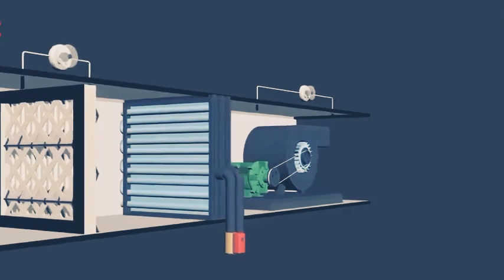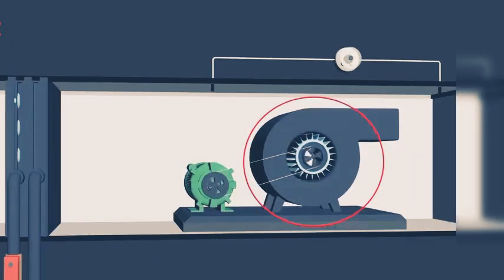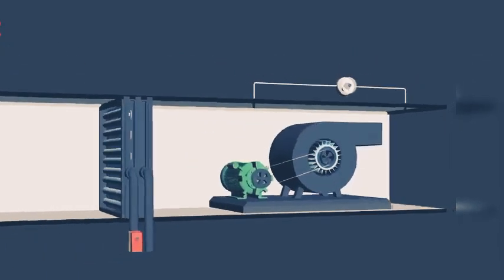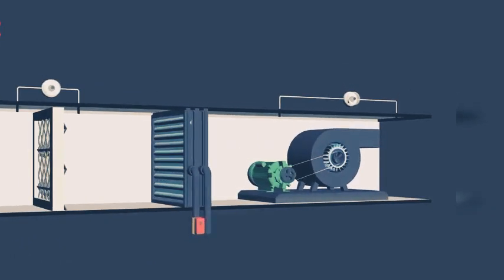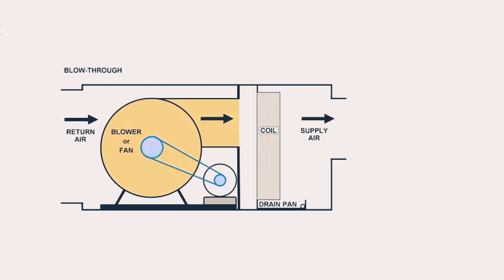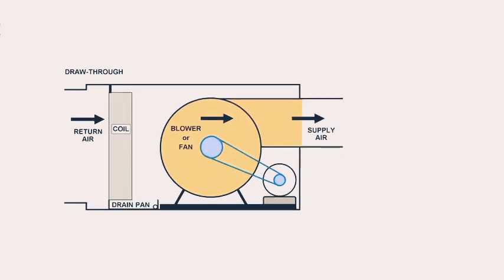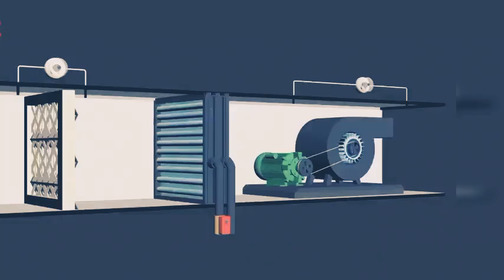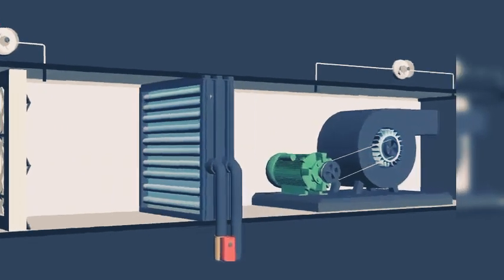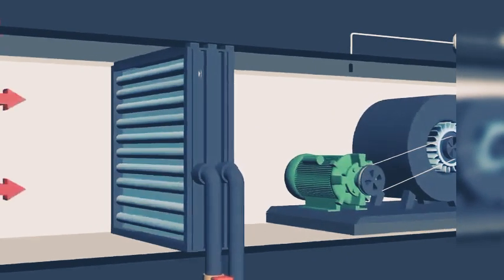A fan coil unit is a device consisting of a heat exchanger coil and a fan. Fan coil units fall principally into two main types, blow-through and draw-through. As the name suggests, in the first type the fans are fitted behind the heat exchanger, and in the other type the fans are fitted in front of the coil such that they draw air through it. Draw-through units are considered thermally superior, as ordinarily they make better use of the heat exchanger.